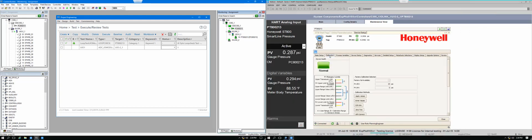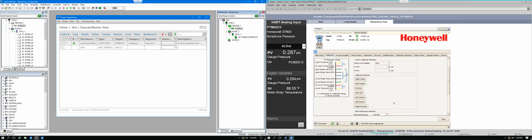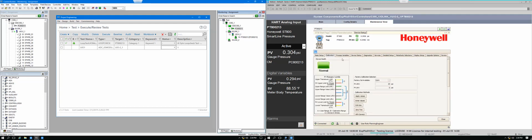Loop check 100%. Okay, then for calibration, you can go in here and trim it up if you're not where you need to be. And then you can view all your process variables - primary, secondary, tertiary, and analog output meters here.